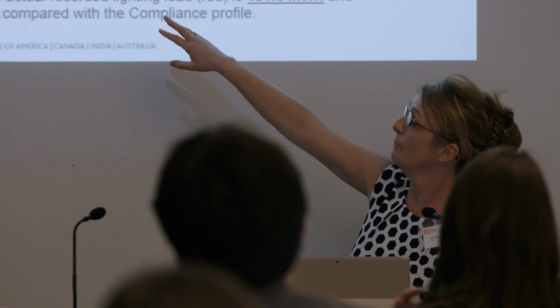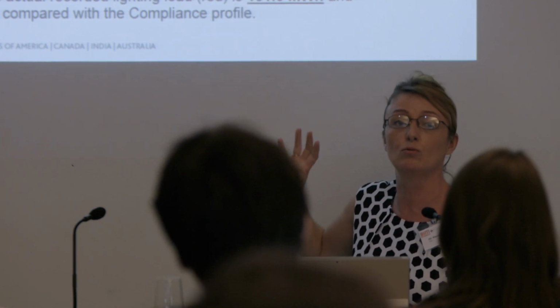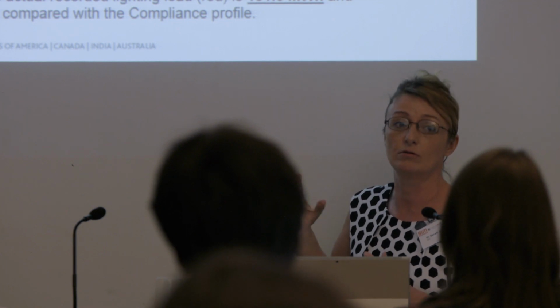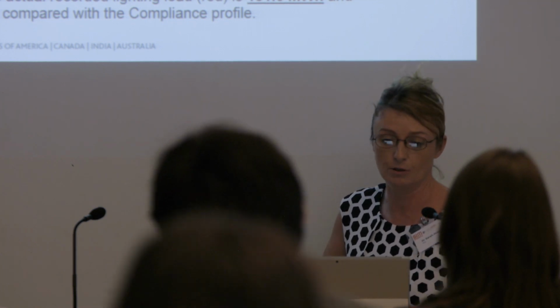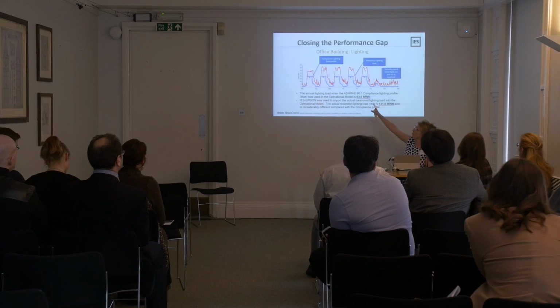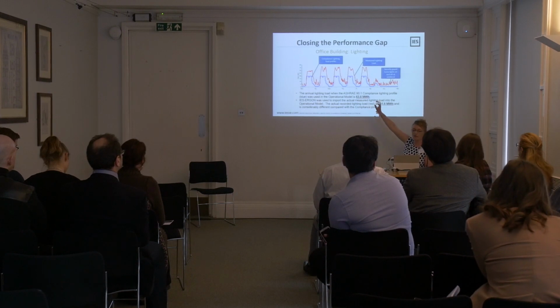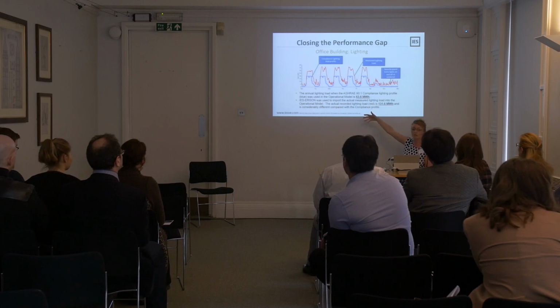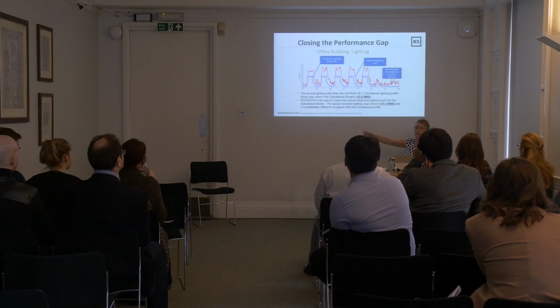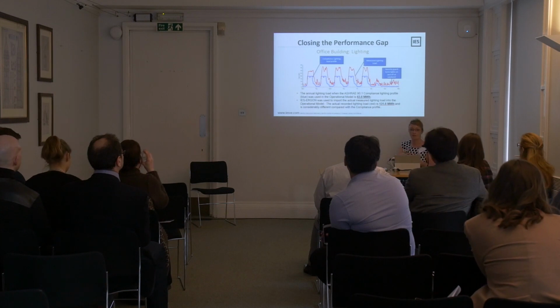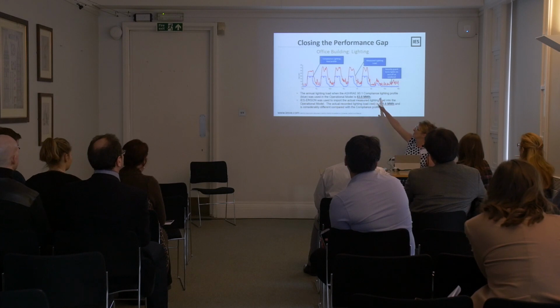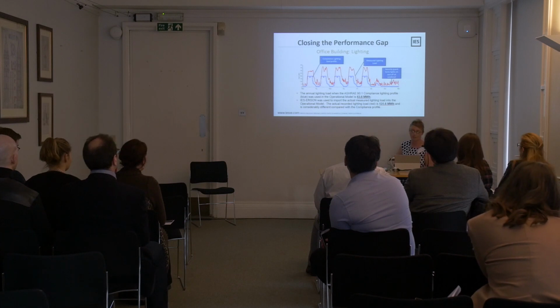The blue line is a typical design stage assumption for a lighting profile in an office, so we can see it drops off at weekends and things like that. The red line is measured data from the building in operation. We've pulled that data back into the simulation software so we can compare the two, and we can see the pattern is not that different.